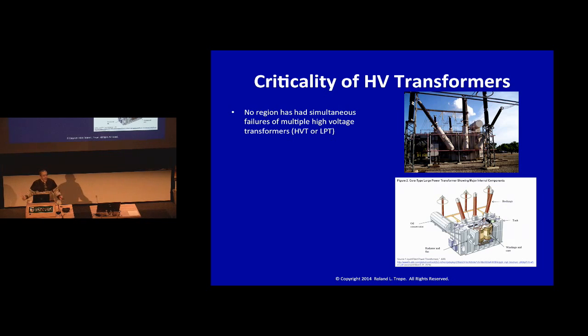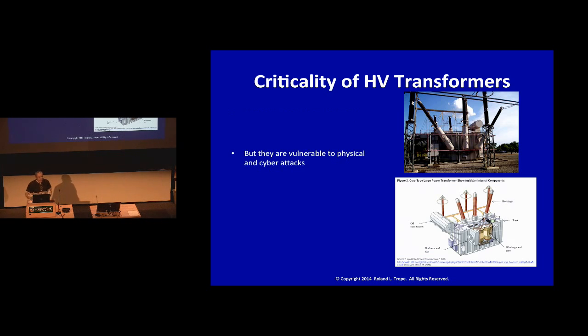They're not maintaining a large inventory of spares. These are vulnerable to both physical and cyber attack. Some of you may have read about the Metcalf substation just outside Silicon Valley, which is the choke point for electricity going into the valley. Snipers attacked that about a year and a half ago with rifles at about 1 or 2 in the morning, and in a matter of 9 minutes knocked out 17 of the high voltage transformers. Had they not been able to reroute current around, the entire Silicon Valley would have been out for as long as that station was, and that station was down for 29 days.